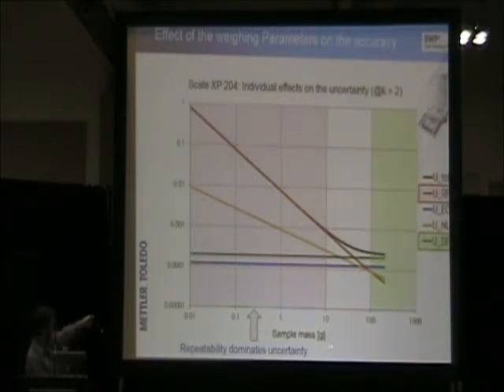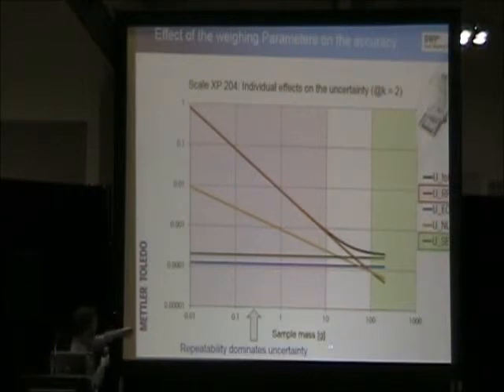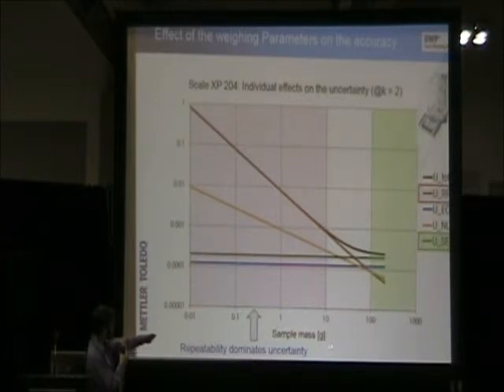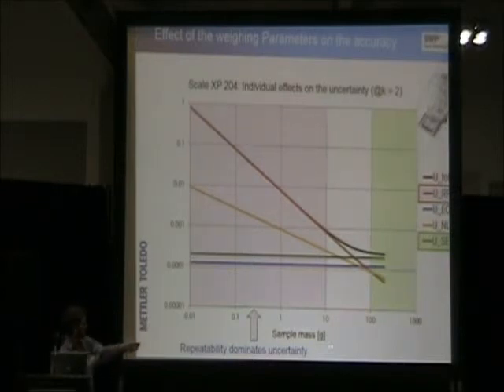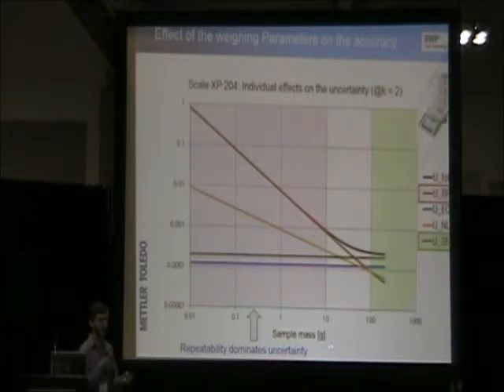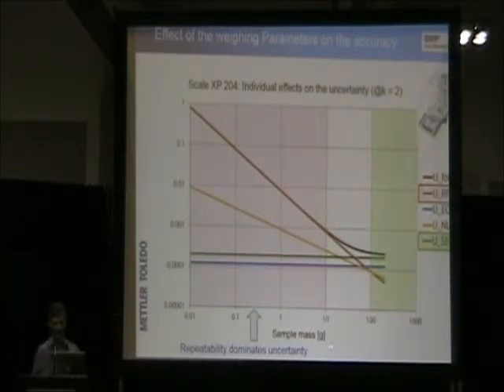Repeatability, which is the red line here, is most dominant on the low end. For this particular instrument, which is 220 gram capacity, once you get below 10 grams, the other three parameters have very little effect on your total uncertainty. Repeatability is essentially your total uncertainty below 5% of your capacity. So when you do routine testing for repeatability, you want to test below 5%. When you do daily spot checks with a calibration weight, you want to test as close to your capacity as possible to ensure that your total uncertainty is being evaluated.